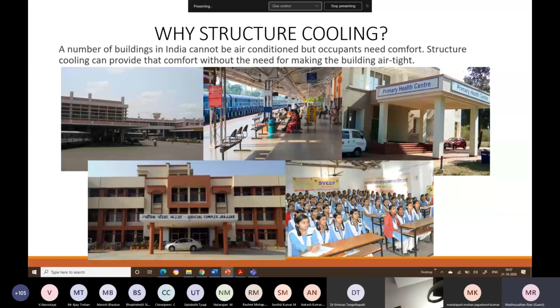So if we just flush the heat out from these buildings, and just use a fan, we can be comfortable. Because structural cooling consumes only 0.05 kilowatt per ton of cooling, whereas air conditioning consumes around 1 kilowatt per ton of cooling. That's around 95% less energy consumption, which should make it affordable for most buildings.